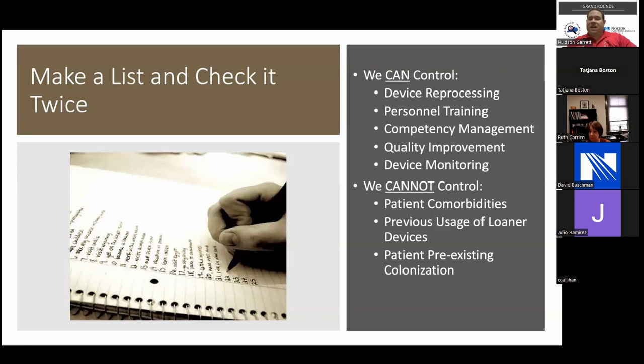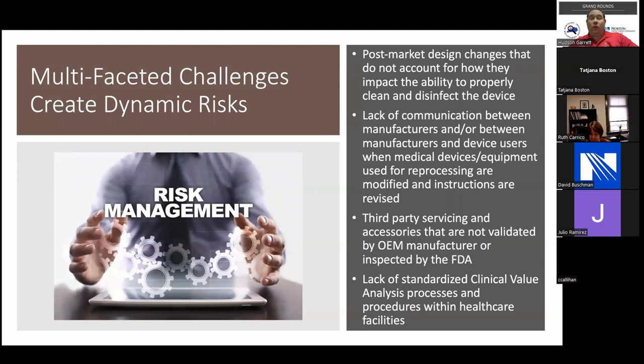And a lot of this went back to holes in FDA's own regulation. FDA does allow third party reprocessing as well as repair. Unfortunately, neither of those areas is actually regulated by the FDA. The first time I heard that, I literally spun my head around and thought, I could not have heard that correctly—that could not be right. So we regulate the device manufacturers, but we don't regulate any of the people that service and maintain the device outside of that initial realm. And so there was discussion about 5 years ago for FDA to start regulating.